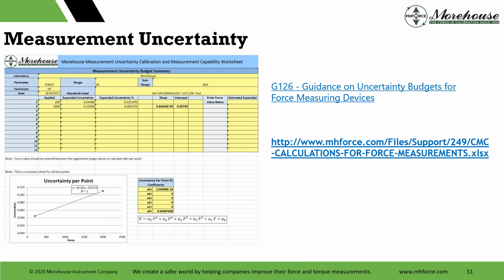We have guidance. It's available. This G126 is an A2LA guidance document. It will walk you through everything that is needed for not all cases, but most cases for uncertainty. Those done in accordance with ASTM E74, the ones that we discussed today with tolerance, the ones for a load cell or transducer with non-linearity, SEB, hysteresis, all that.